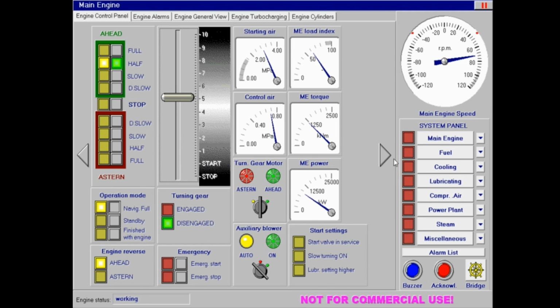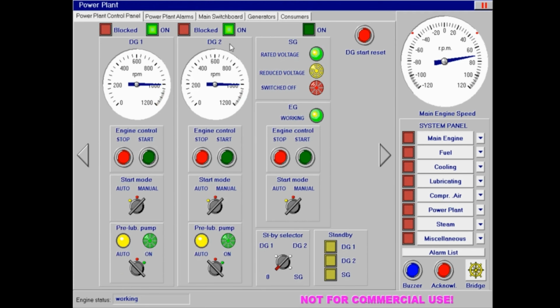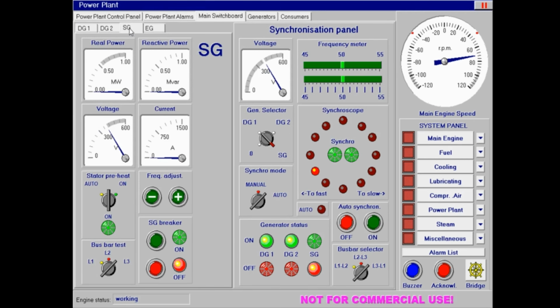as well. So we're going to power plant, click on main switchboard, click on shaft generator, go ahead and turn on the stator, get it all nice and warmed up before we actually engage electricity to it. Shaft generator is selected, then all I've got to do is make some. It's auto, hold the on key. Now you're seeing this little dot rotating, which represents phase. Once it gets up completely in phase like I just did there, it's going to come up. So now we're actually running off the shaft as well as these two generators.